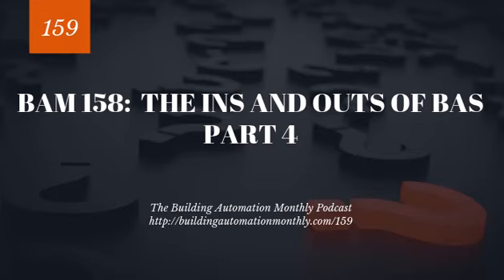So your typical building automation system server is going to be comprised of three pieces. Piece number one is going to be the application server. This is going to be the building automation application. This is what is going to run the core code of the building automation software. So typically this application software is going to allow for your BACnet IP interfaces, your Fox protocol interfaces, your LonWorks EIA-852 interfaces, your Modbus TCP interface, whatever interfaces.